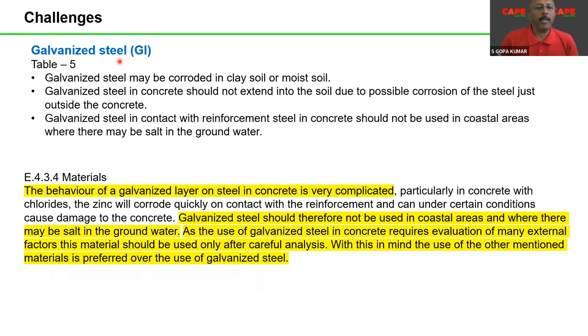Number two, what kind of material do we use? Whenever it comes to the type of material, we always talk about galvanized steel. All of you know GI, which is available very abundantly in India. Now, the recommendation in the standard, table 5: galvanized steel may be corroded in clay soil or moist soil. That means if you use galvanized steel as a natural component, imagine you are making a grid under the building and your building has to be there for the next 100 years.